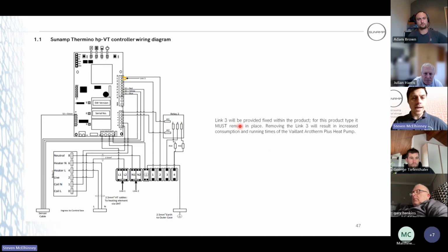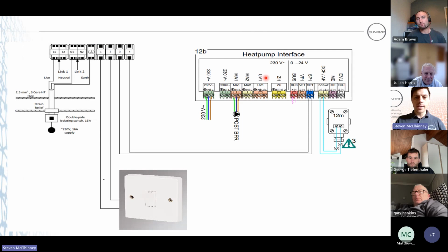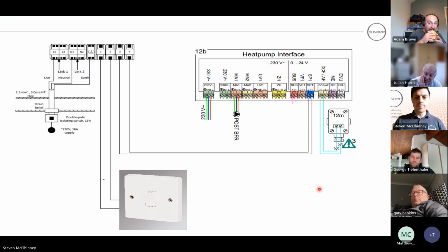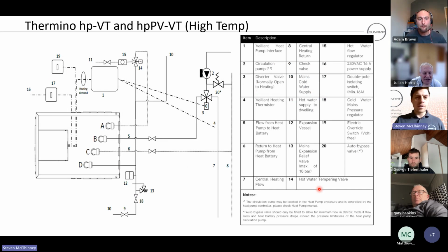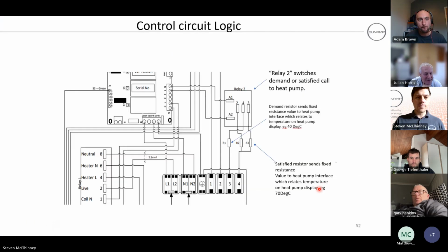One thing to remember is you have to keep link 3 fitted with the Vaillants. Don't remove that. There's no 45-minute time delay for the element to come on. There's no requirement because it's a high temperature heat pump, so you can achieve the flow temperatures, but you have to keep link 3 fitted. Okay, don't remove it. And that's just a basic kind of wiring schematic. You've got your switch for your volt-free signal for the element, and you just wire your 2-core back to SP1, 1 and 2. Another schematic.